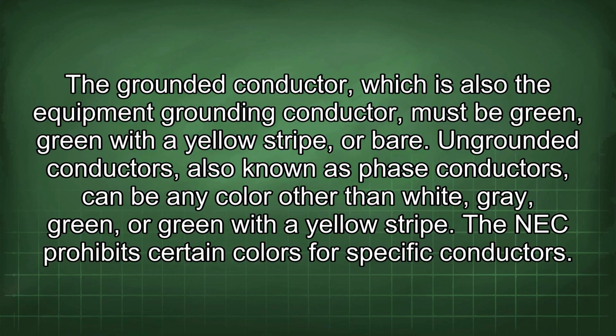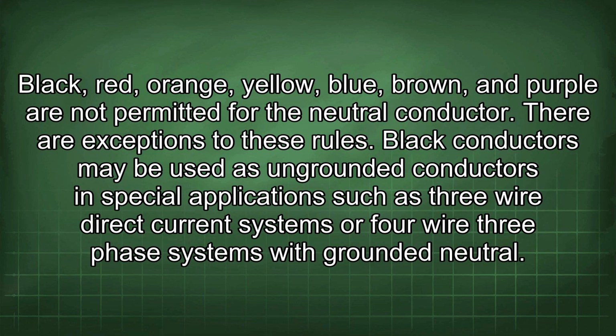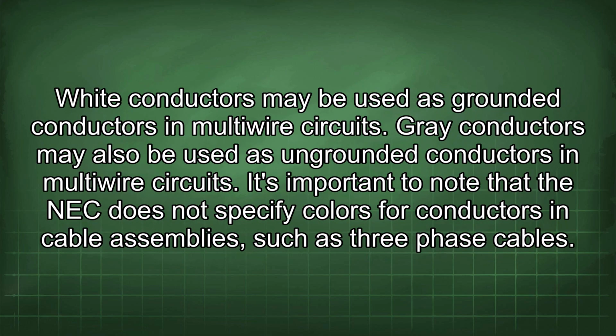Ungrounded conductors, also known as phase conductors, can be any color other than white, gray, green, or green with a yellow stripe. The NEC prohibits certain colors for specific conductors. Black, red, orange, yellow, blue, brown, and purple are not permitted for the neutral conductor. There are exceptions to these rules. Black conductors may be used as ungrounded conductors in special applications such as 3-wire direct current systems or 4-wire 3-phase systems with grounded neutral. White conductors may be used as grounded conductors in multi-wire circuits. Gray conductors may also be used as ungrounded conductors in multi-wire circuits.